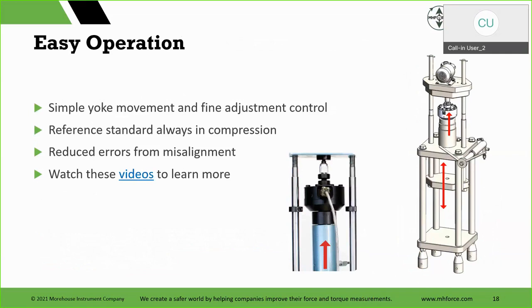So it's really your reference standard only needs to be in compression. That calibration is much less expensive than a compression and tension. Not to mention, you're conditioning that reference standard, so it's always in; you don't have to do the switch. That material is never being pulled on, so it's going to be more uniform. It's going to repeat a lot better. That load cell only sees compression for its lifetime. You don't have to switch and then re-exercise. It's going to condition, it's going to become really flat.